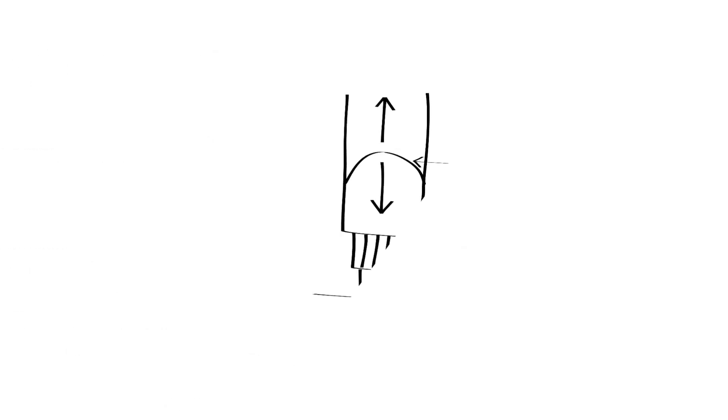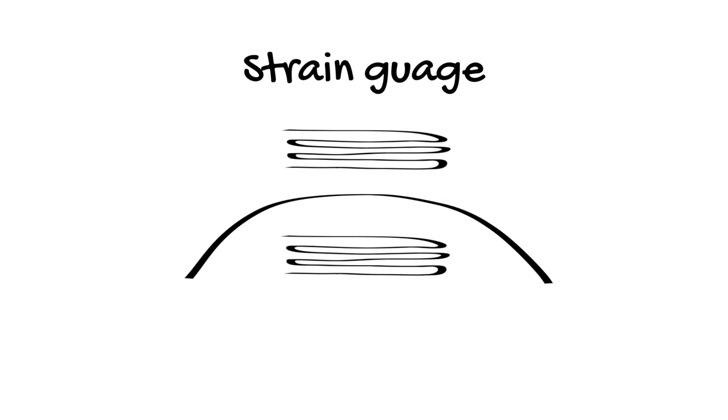The transducer contains a flexible diaphragm which is pushed up and down by the continuous column of fluid as it moves through the cardiac cycle. On either side of the diaphragm is a component called a strain gauge.